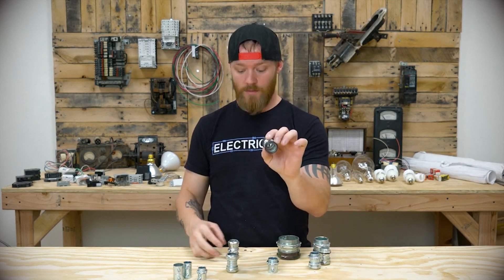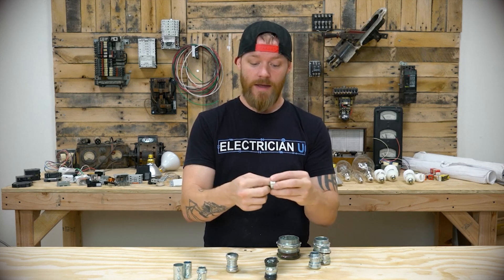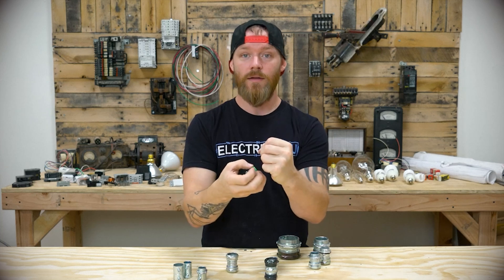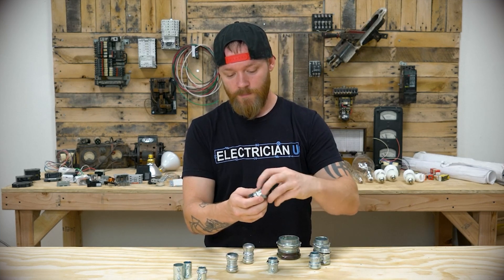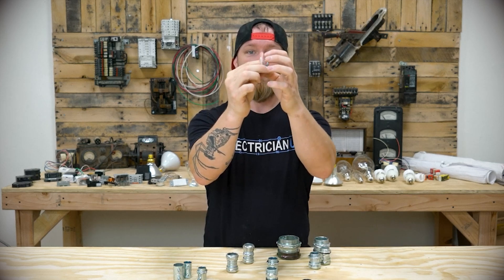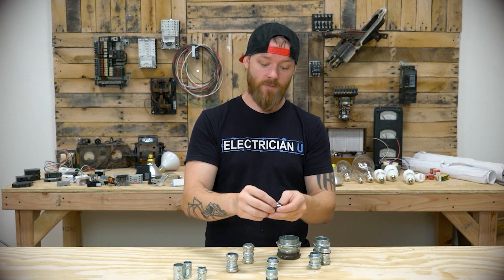Instead, you have newer style compression couplings and connectors. They've had to do some things to get away with calling their stuff rain-tight. So this one has an extra little plastic ring inside of it — once you put this on and tighten it, it actually cinches around that conduit, which allows moisture not to penetrate into the conduit. This other one does it a little differently — it still has a plastic ring but also has two different metal rings. There's a little metal ring that kind of pushes the piece down, and then a compression piece that tightens over the conduit. A lot of different manufacturers do different things to get their UL listing for rain-tight.